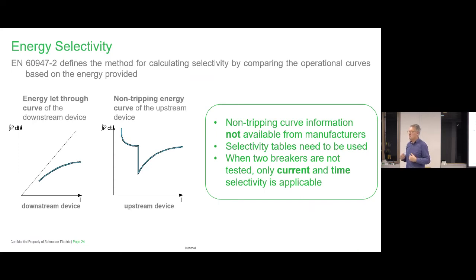Even with our own breakers, we'll say to you, well, two breakers not tested. We have new offers coming in all the time, and we're not always testing them straight away. We don't see the benefit maybe in this offer with all of these. Generally speaking, we like to test as much as we can, but not everything we do. And if we can't give you that, we say, well, we haven't tested between those two devices before because we hadn't thought they would ever be used that way. But industry always has a way of finding that they do, and they say, no, that would be perfect for us, and we'll do that.